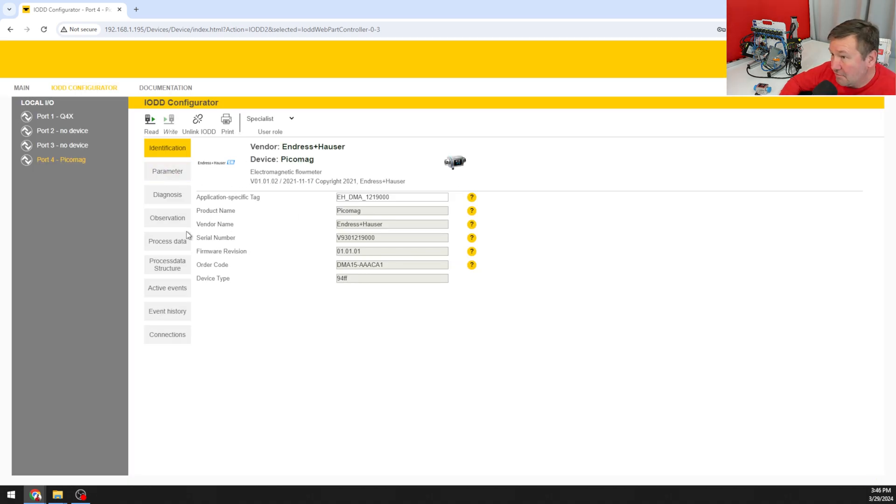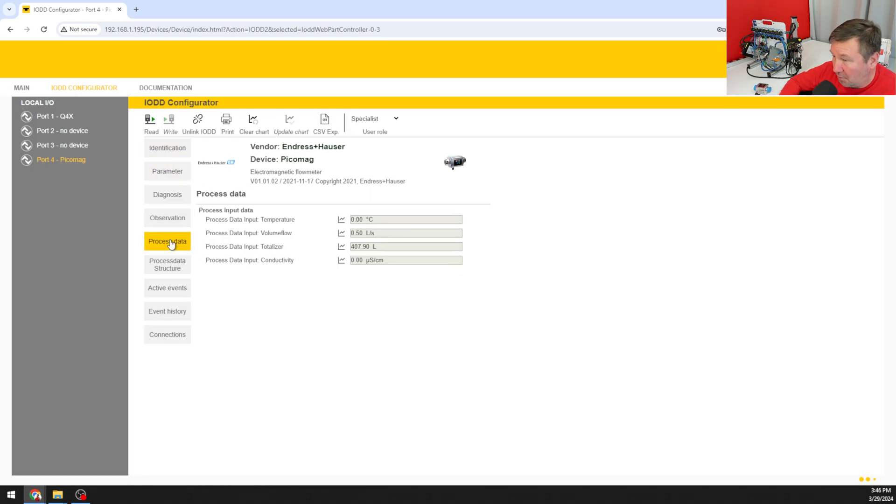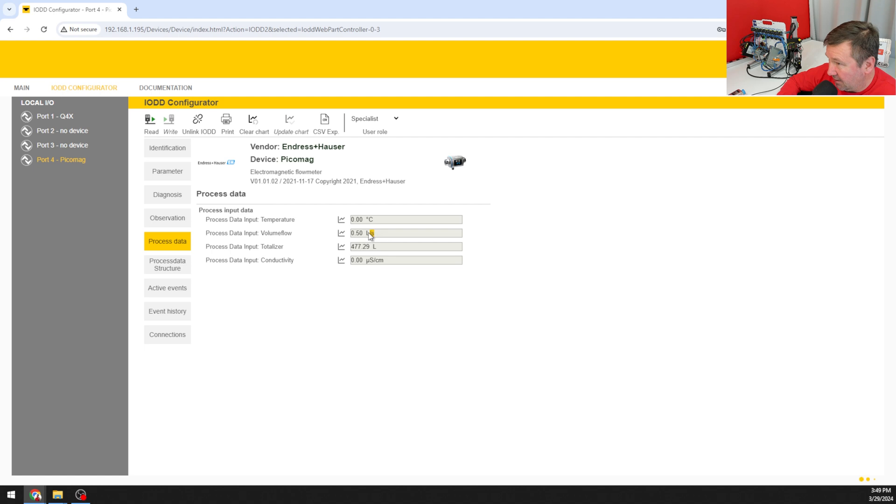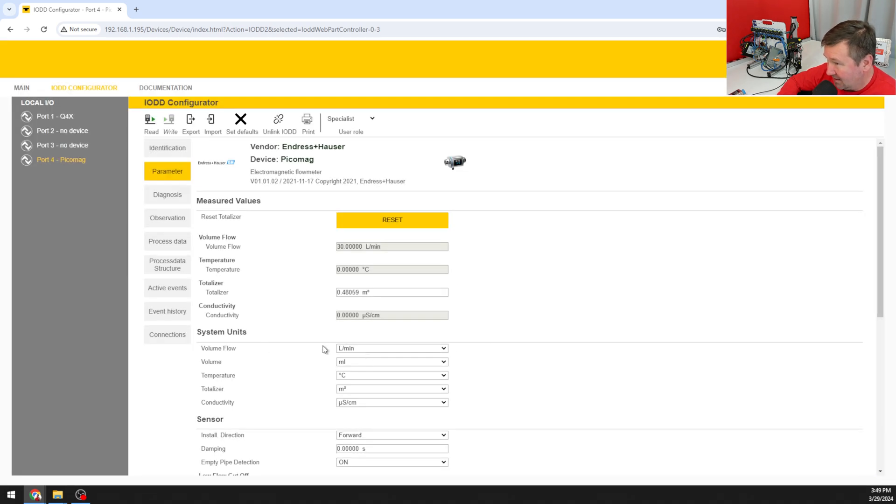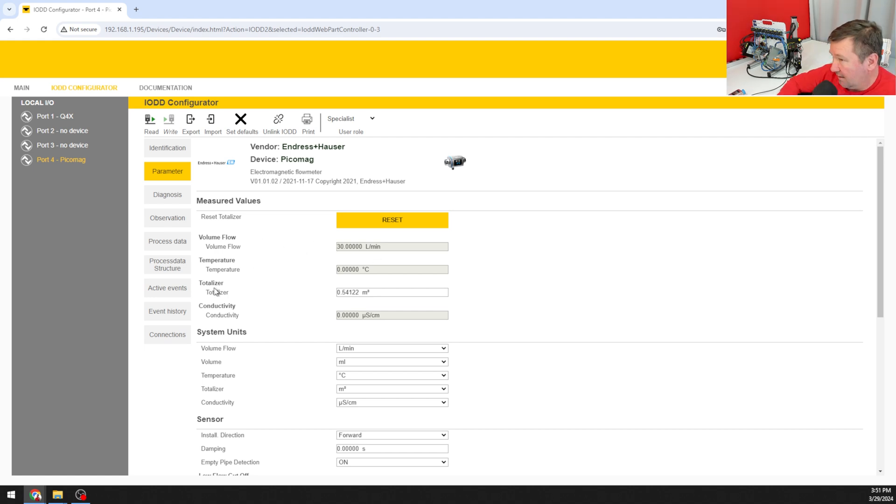Now we can go down to our process data and we can see the actual data coming across. Notice here it is in liters per second coming across on the process data. But on our parameter tab we can actually select the units that we want. I'm on liters per minute and that means it's going to be reporting liters per minute.